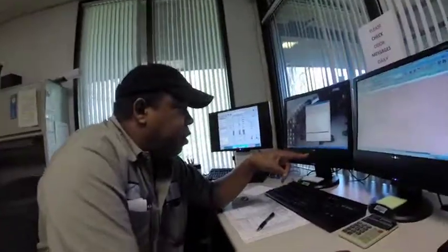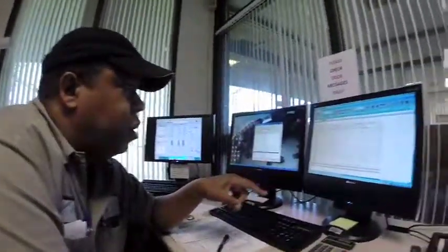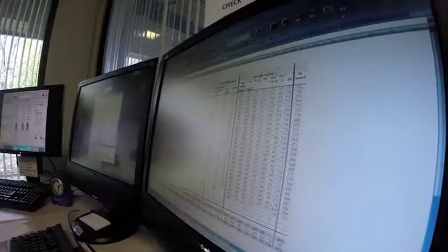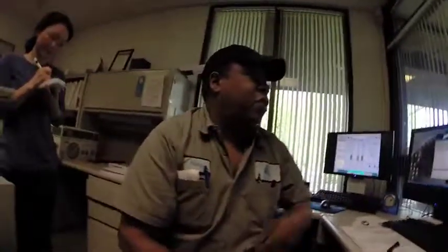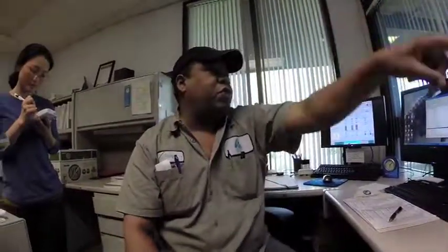You want to know about the detention time. It's right there. Aeration basin detention time right now is 6.4. Secondary clarifiers in there for 6.7. The total secondary system is 13.1. It's already calculated out there for us, so it's the way to go. And right now I'm running about a 41% return rate from my clarifiers back over to the aeration basins.